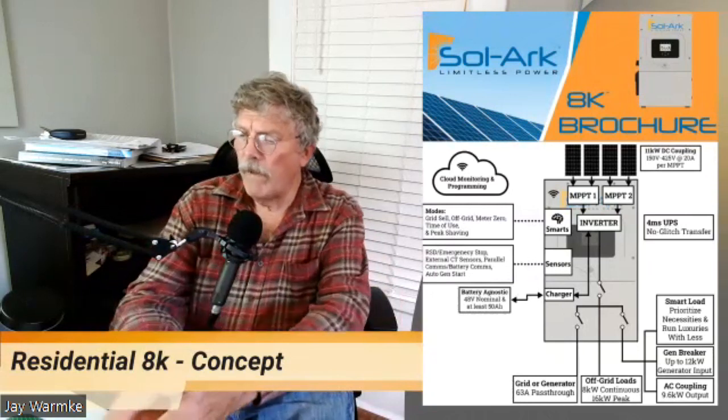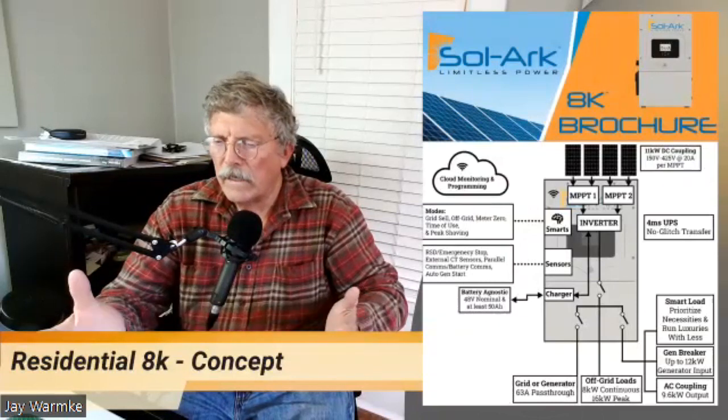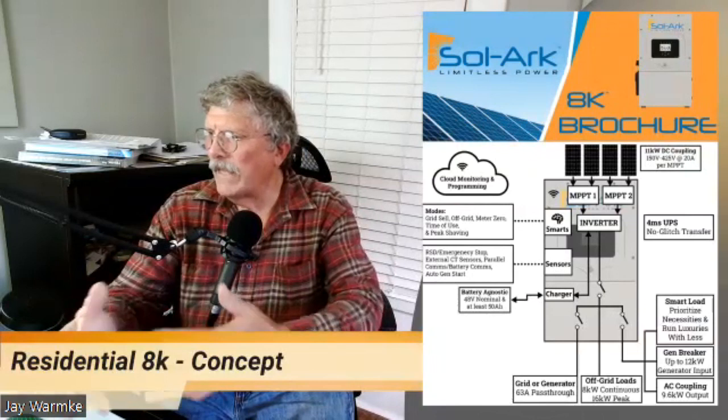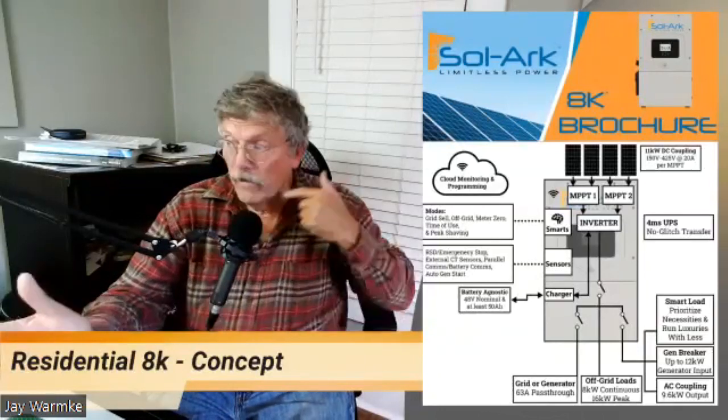But then if you do have battery backup of some sort, then you've got to have some sort of DC disconnect out there at the meter as well, because obviously you disconnect the AC, the system's designed to go into standalone mode, so now it's still operating, but they want that turned off as well. So usually now you've got to have an AC and a DC disconnect out by the meter, which is a bit harsh. But I agree with you, Ben.